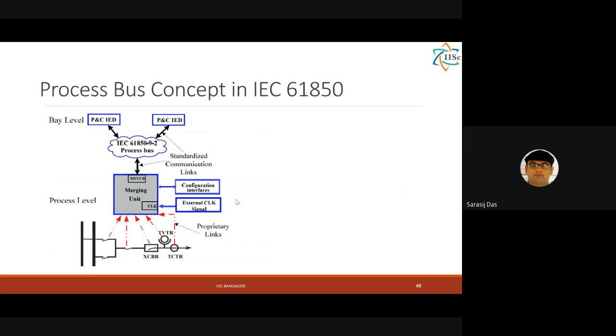Okay, so now if you focus on the process level, in this level the main change has happened. In a conventional substation, from the CT and PT secondary, we take a copper cable which carries the analog signal to the substation control panel. So this whole cable carries your analog signal. Now, to reduce the amount of copper cabling, the standard proposes that instead of bringing the copper cable to your control center and converting its analog signal into digital, why don't you convert it in the field itself, near the CT and VT?